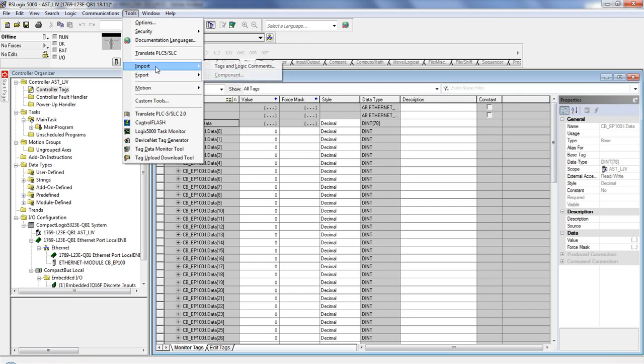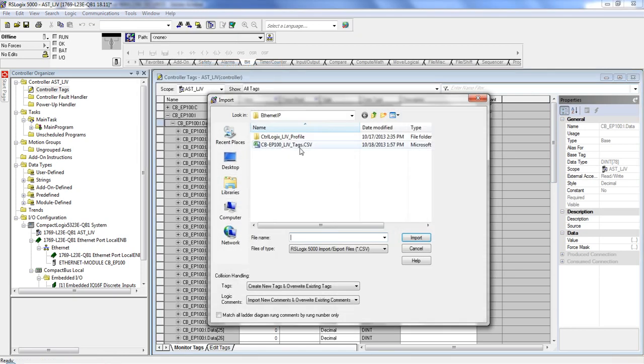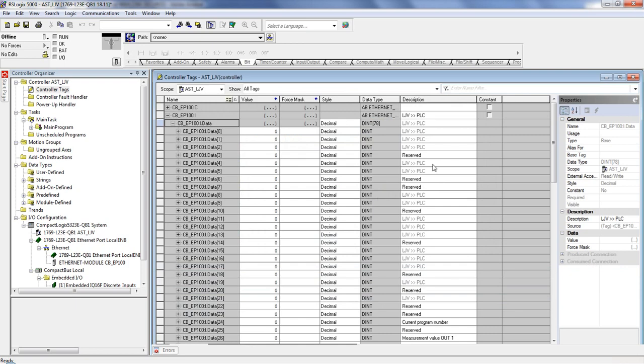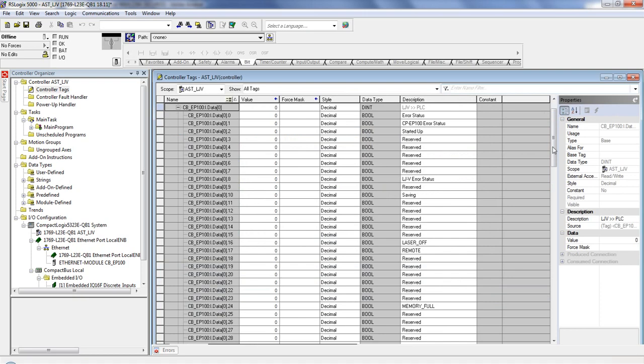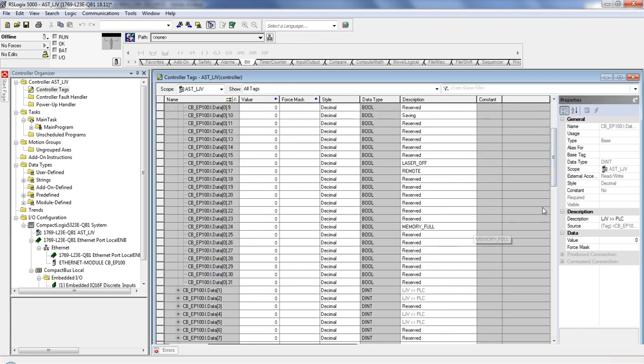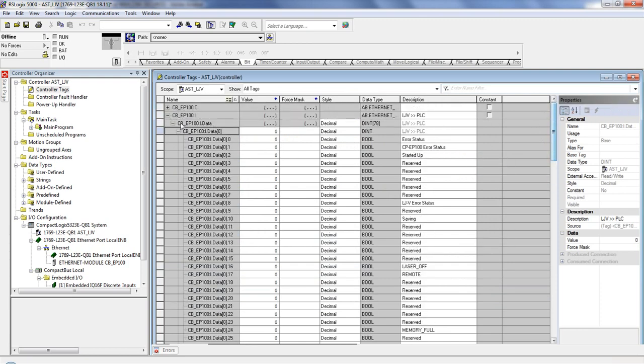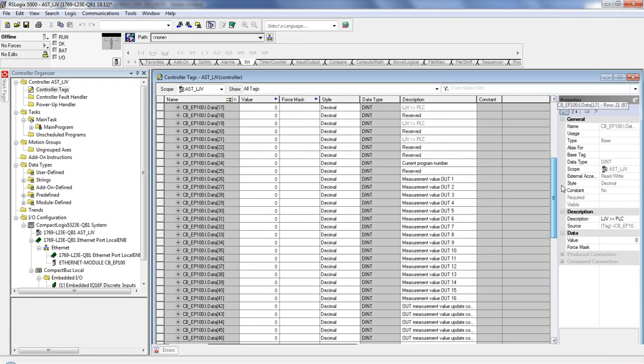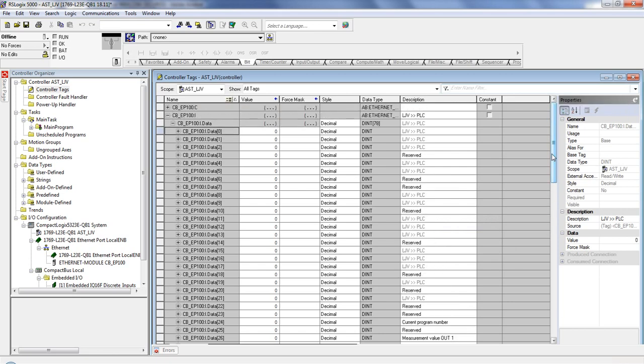The next step that you will want to do is TMG has prepared all the tags for all this data. So all this data currently has no label. So to import the tag, we're going to do Tags and Logic Comments. And we're going to choose this file here. You can leave all of these as default. Choose Import. You're going to see all of these are populated. So now if I were to click into, say, this one, I now see that this bit right here is an error status. And here we see everything is labeled out. And for example, if I were to go to my measurement values, here are my measurement values. So this is something that your customer can now do so that they can easily view where all of our data is.